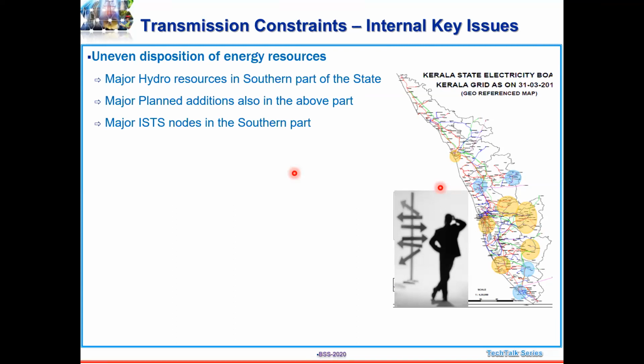And that is one major concern for us, because every grid requires reactive support for voltage, for providing the required voltage. So the reactive power is being provided from the generating stations and a little bit from ISTS also, because ISTS nodes won't allow any reactive flow to occur through the interconnecting transformers. So basically all the reactive power has to come from the hydro stations.